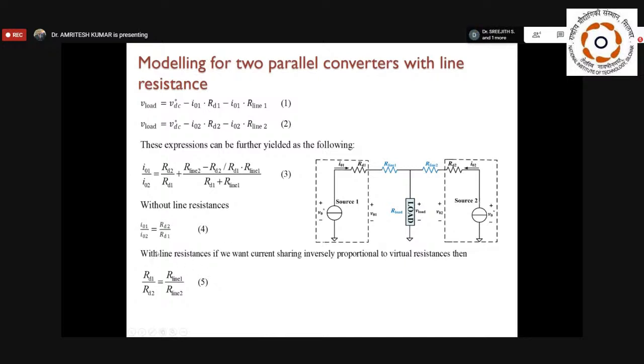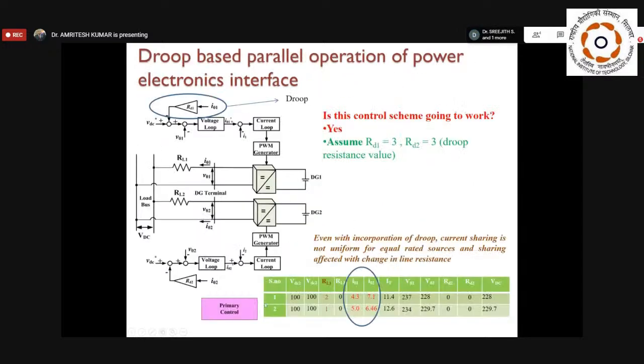Now, with line resistance, suppose we incorporate the line resistance in the system and we want to share current inversely proportional to virtual resistance. One important aspect I forgot to tell: when we are incorporating the virtual resistance, you can see in cell number 1 there is a line resistance I have included, which I marked in red. With the same droop value, 3 ohm only, if I change the line resistance RL1, suppose initially it was 1 and now it is kept at 2, then you see the current sharing. Is it the same? No. It means that even though you have incorporated the droop, if we change the line resistance, the current sharing increases or decreases.